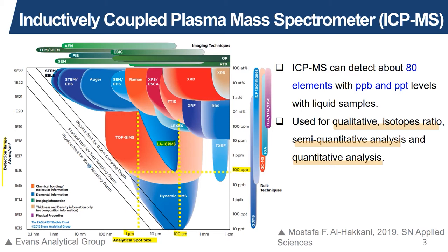For typical ICP-MS measurements on liquids, the chemical sensitivity can go down to an astonishing order of parts per trillion, tracking down even a smidgen of impurities within the solution. However, in the case of liquids, the analytical beam size is effectively meaningless, as elements can freely diffuse with little to no resistance within the liquid matrix. Hence, the ICP-MS measurement for liquids or bulk does not appear in the 2D bubble chart but can be seen on the 1D plot next to it.